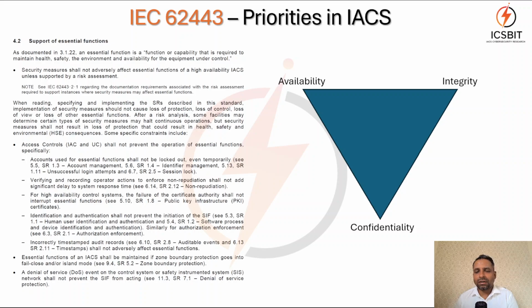When we are certifying a device for safety, that is safety integrity level, we check availability through integrity. For example, fuzzing. We use tools like Wurldtech Defensics, Wurldtech Achilles, and Defensics Coordinator. These tools have a couple of hundreds of thousands of use cases to check the integrity of the communication protocols.